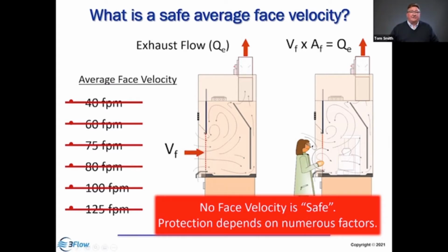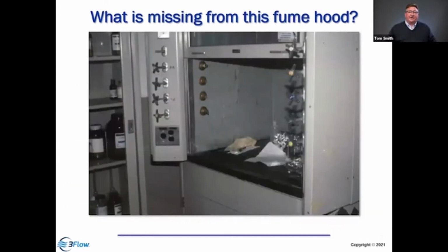If you multiply that velocity times the area of the opening, that's the exhaust flow. So, the velocity times the area. If you have 100 feet per minute velocity and a 10 square feet opening, say 5 feet wide, 2 feet tall, that's 1,000 CFM of exhaust. That doesn't say anything about containment. It doesn't talk about the degree of protection provided. It's just a velocity. And we have to think about other factors that could influence the containment capability.